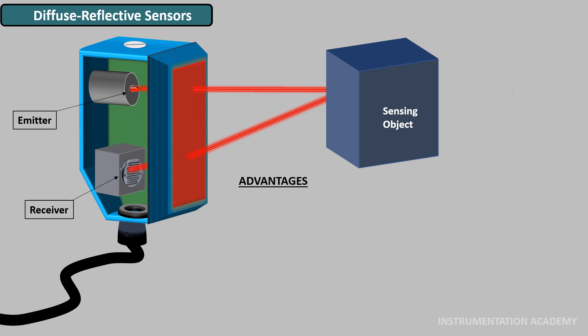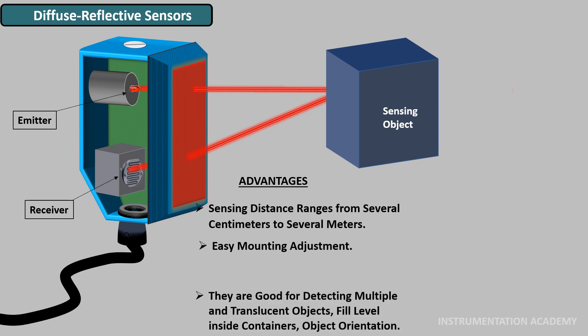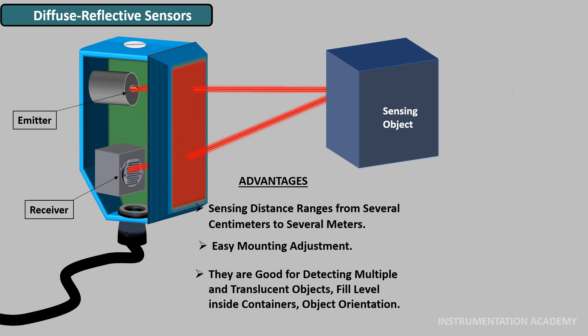Advantages of diffuse reflective sensors: Sensing distance ranges from several centimeters to several meters. Easy mounting adjustment. They are good for detecting multiple and translucent objects, fill level inside containers, and object orientation. Disadvantages: Sensing can be affected by color, texture, dirt, and other factors.